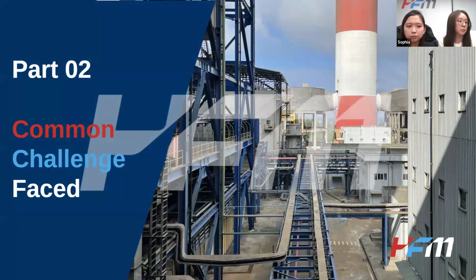So in part two, we will talk about some problems in the installation process. Now I have a question for you, Susanna. Have you ever encountered cases where a plate heat exchanger's performance has deteriorated due to an installation problem? And how can this problem be avoided? Well, I do have experience. I once came across a client who installed the heat exchanger gaskets in an improper way. This caused his heat exchanger to be totally damaged and also caused severe leakage. So during the installation process, it's really important to ensure that there's no damage or improper displacement. Okay, thank you.